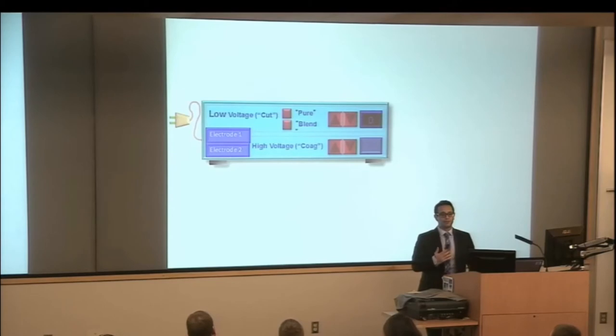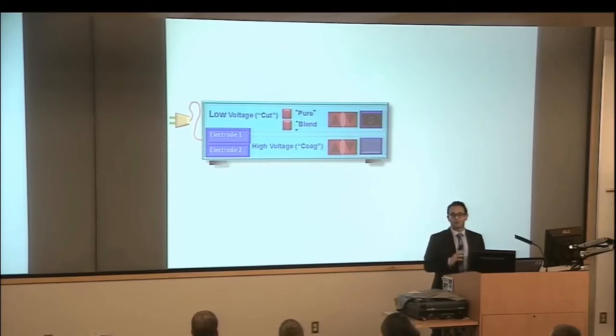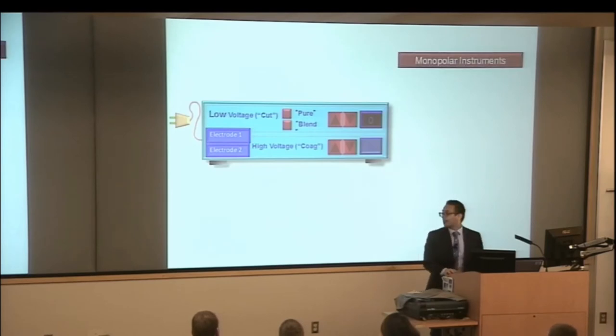So what's the difference between monopolar and bipolar instruments? The truth is, every radiofrequency device is bipolar. There's actually not a true monopolar device - everything's bipolar, there's always two electrodes. The only difference is what's the use and function of that second electrode. We'll demonstrate that right here.